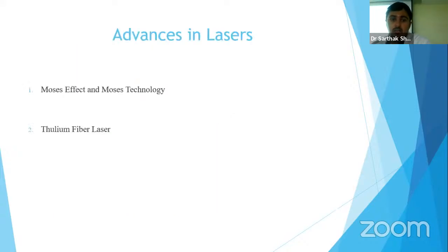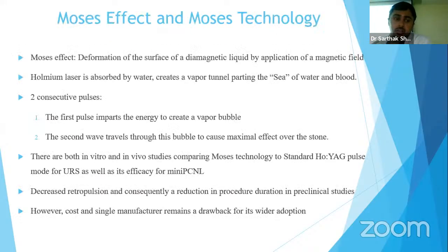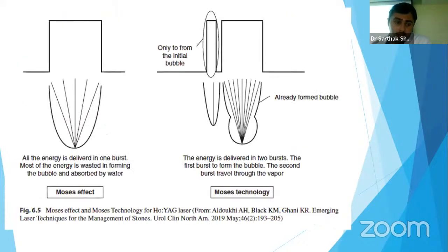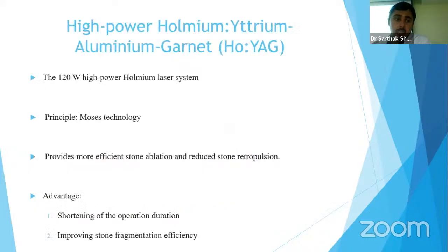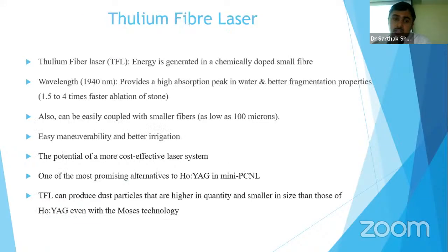Advances in lasers. Major advances have been in development of Moses technology and the thulium fiber laser. The Moses effect utilizes all the energy in the formation of the bubble, and the energy is totally absorbed by the water. To overcome this, we created a system that delivers energy in 2 bursts. The first burst is to form the bubble, and the second burst travels through the vapor and helps in stone fragmentation. Using this technology, we developed the high power holmium laser, which has a 120-watt high power system. Its advantages are shortening of the operative time and improved stone fragmentation efficiency.